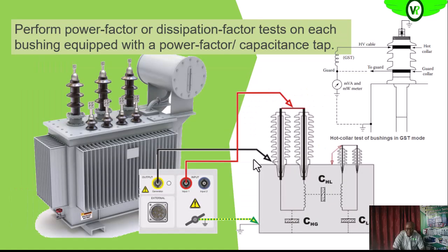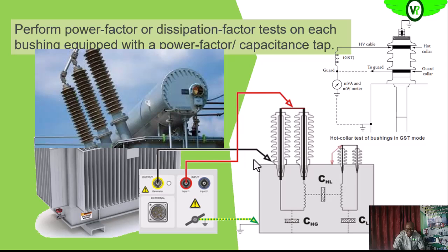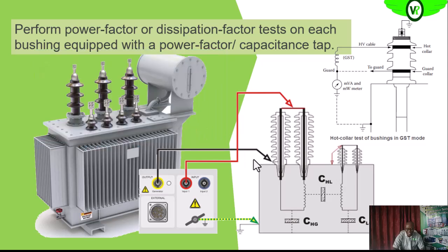We also do the same for the bushings. It is the same thing. Basically, why this is important: if we have cracks on the bushings, this power factor or dissipation factor test will expose such cracks. So we want to carry out a power factor test on the bushings. What we are looking at is the insulation between the conducting part and the ground, and the external part of the bushing, so to say.